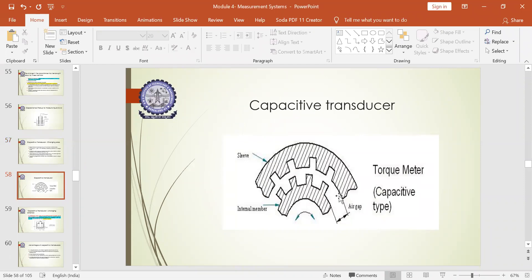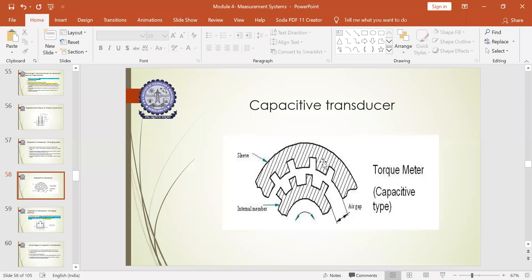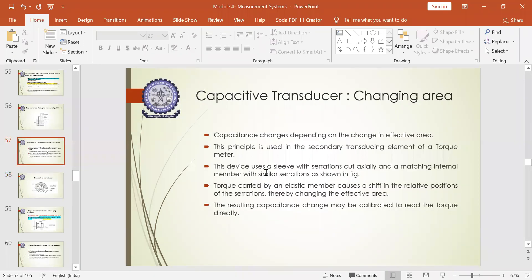There is an internal member and an external member with a specific air gap between them, along with serrations. Due to the variation in the serrations and the associated air gap, it can rotate either clockwise or anticlockwise. The torque carried by an elastic member causes a shift in the relative positions of the serrations, thereby changing the effective area. In the serrations mode, the change in effective area comes into picture, varying the torque. The resulting capacitance change may be calibrated to read the torque directly.